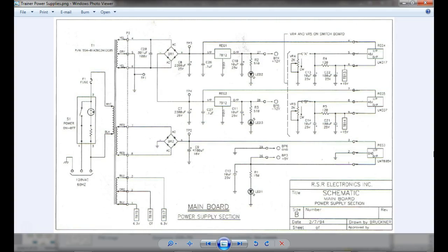The primary is giving us the power at a lot higher voltage, right? You understand that? So this gets people confused. I've seen people do that. They got an 8 amp power supply and they think, by George, they got to use an 8 amp fuse on the primary.